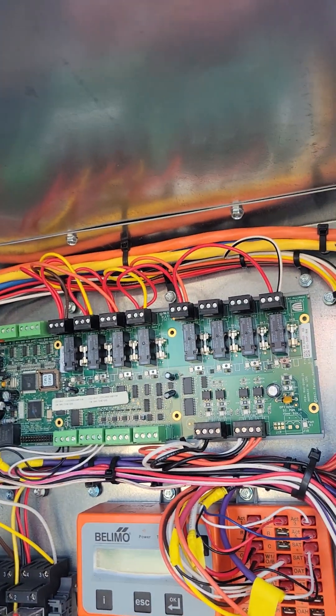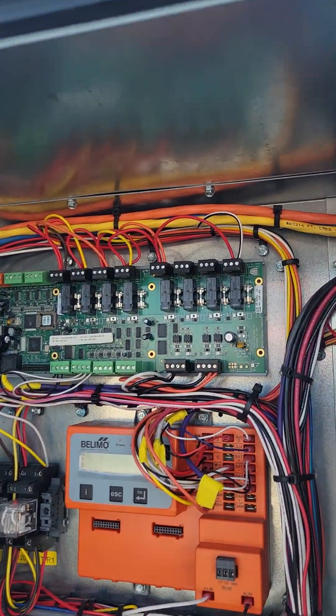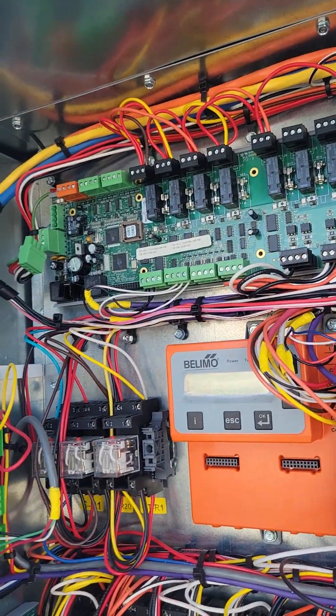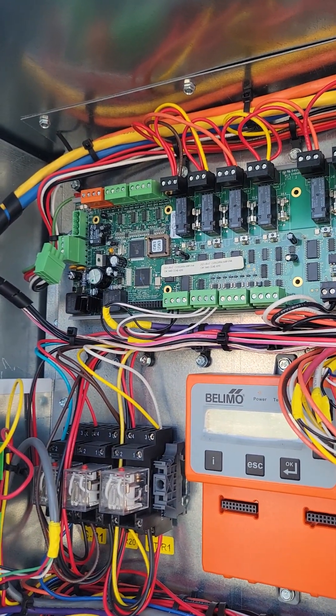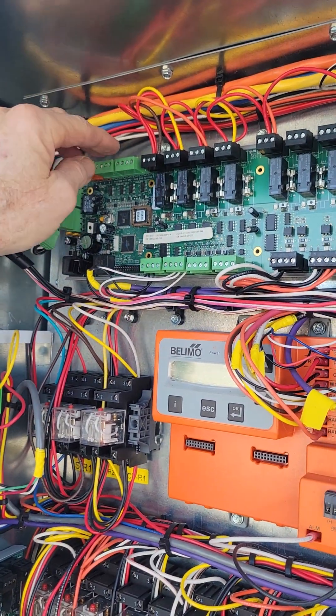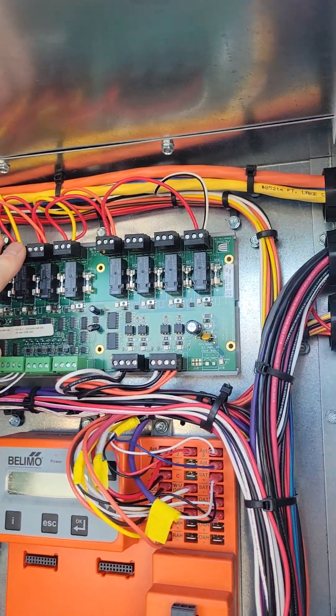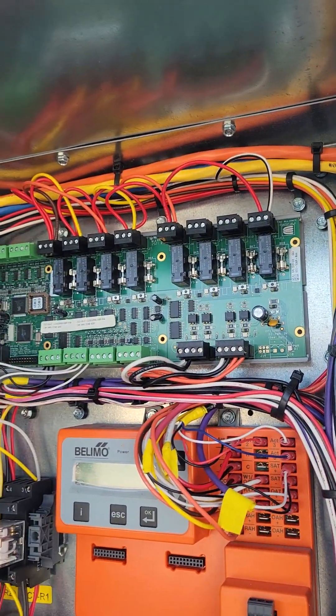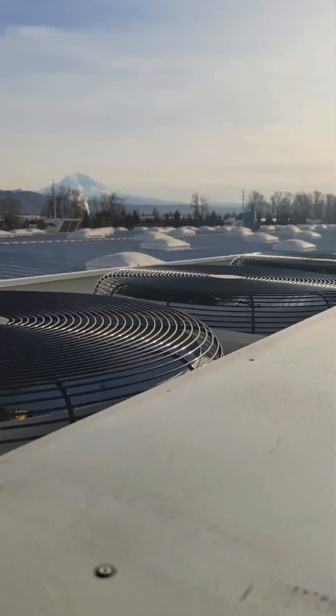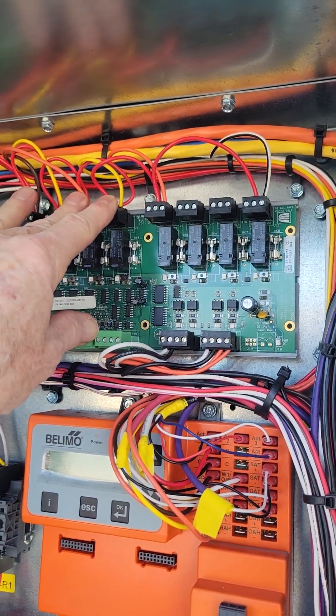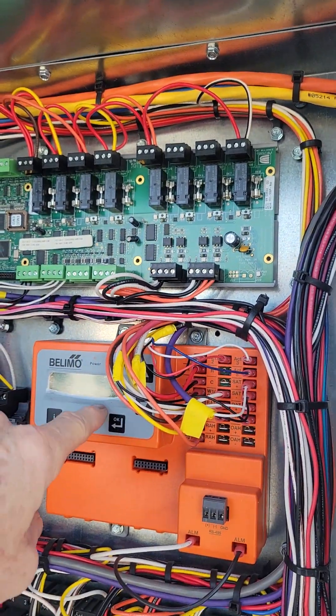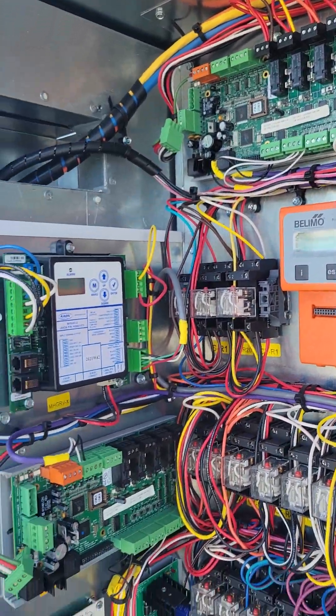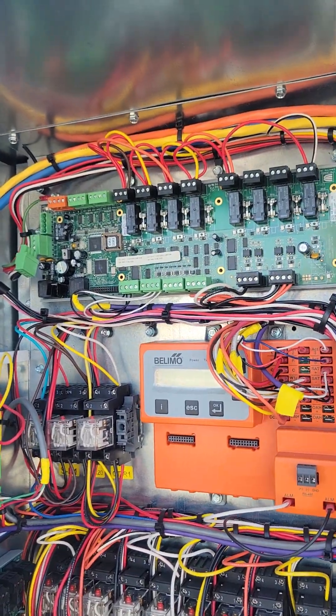So it's kind of sensitive to electromagnetic forces from the outside. In fact, we've had these boards moved away from this line. This is the line voltage for the condenser fans over there. These boards, newer versions are mounted down. I think they trade spots with this board to keep them away from the line voltage.